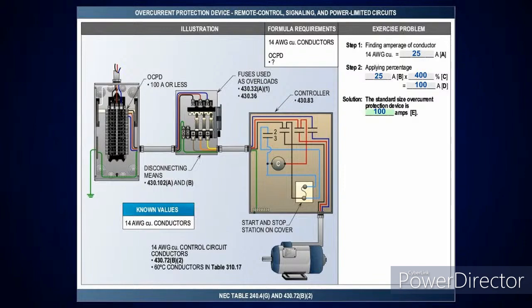So if I look at a number 14 conductor and I pick up table 310.16, it's going to tell you it's good for 25 amps. But now when you're looking down at your note 2, it tells you it's based on what? 400%. So if I take 25 amps at 400%, it's going to tell you it's a 100 amp overcurrent device. Then if I look at column B in that table, which says conductors within the enclosure, and I come down and pick it up for number 14, what does it say? 100 amp. Wow. Isn't that amazing? This is just proving it to you. Everything I tell you is true.